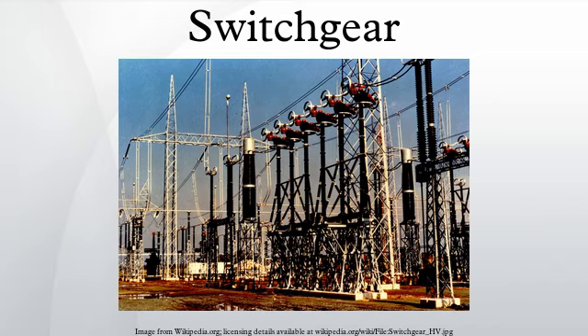Types. A switchgear may be a simple open-air isolator switch or it may be insulated by some other substance. An effective although more costly form of switchgear is the gas-insulated switchgear, where the conductors and contacts are insulated by pressurized sulfur hexafluoride gas. Other common types are oil or vacuum-insulated switchgear. The combination of equipment within the switchgear enclosure allows them to interrupt fault currents of thousands of amps. A circuit breaker is the primary component that interrupts fault currents. The quenching of the arc when the circuit breaker pulls apart the contacts open requires careful design.